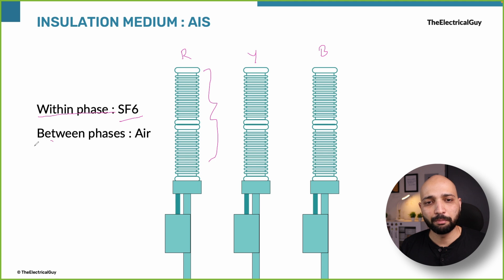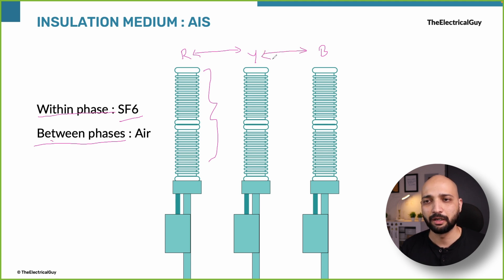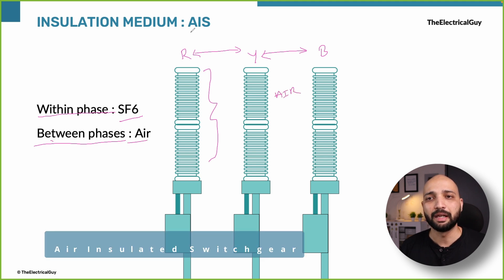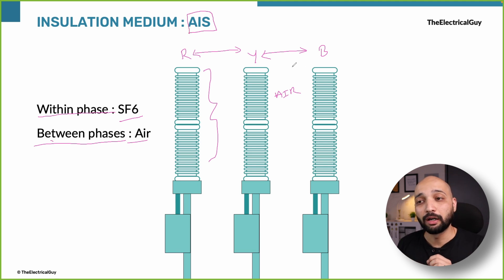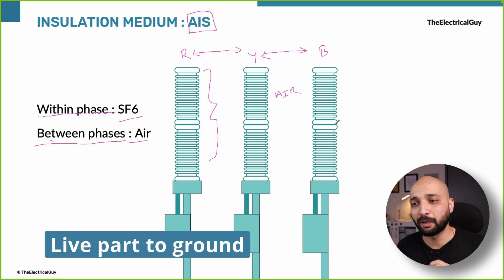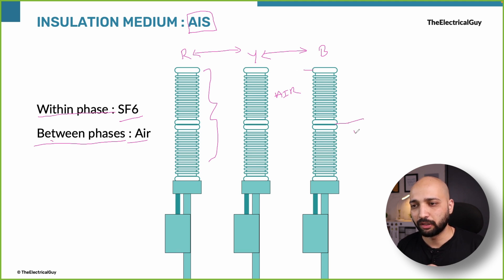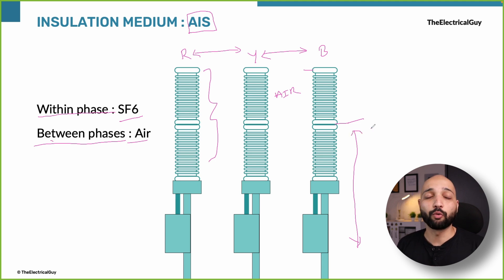The second concept is insulation between the phases — the insulation provided between two phases, such as between R and Y phase or Y and B phase. In the case of AIS switchgear, this insulation is provided by air, and hence the name is AIS or air insulated switchgear. The insulation between live part and ground is also provided by air.